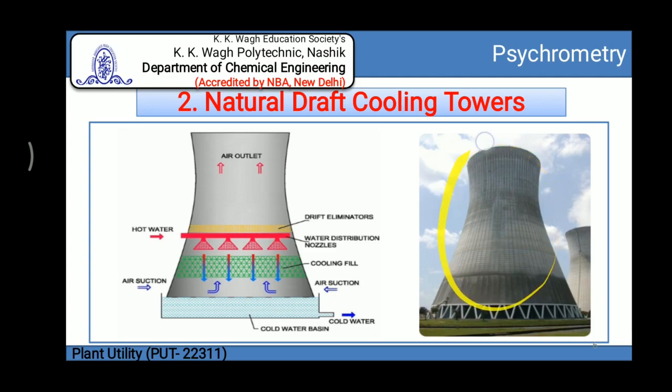You can also see this in the figure. The tower is called so because the movement of air happens naturally inside the tower. The tower consists of a spray mechanism beneath which alternative layers of battens are stacked along with the packing material. Air enters from the bottom of this tower and the water gets splashed when it touches the battens and forms the shape of droplets. These droplets result in a good heat transfer area.